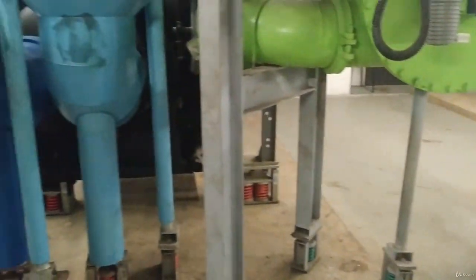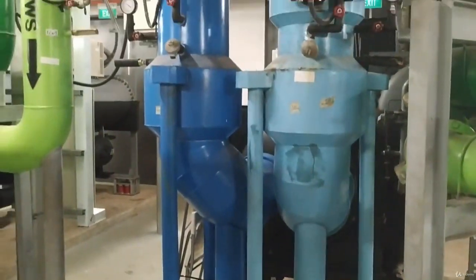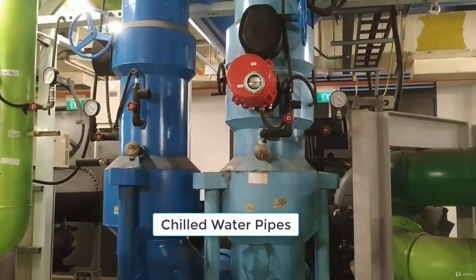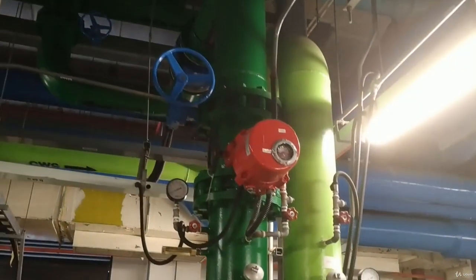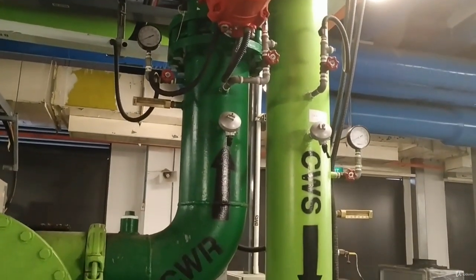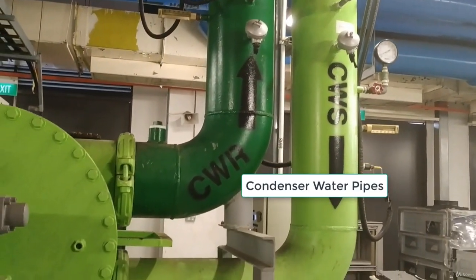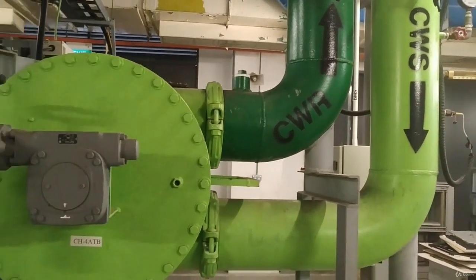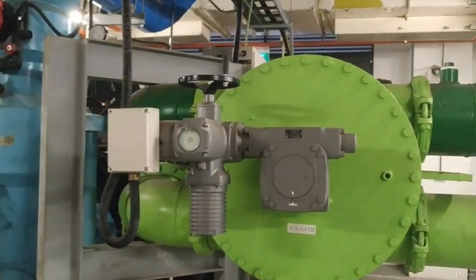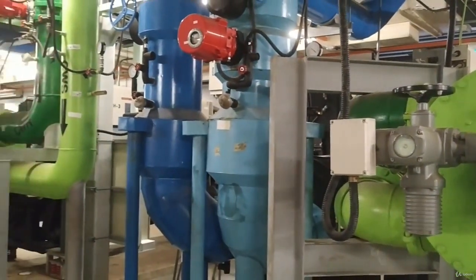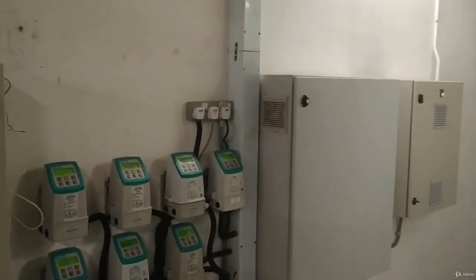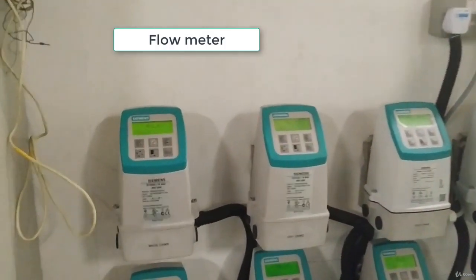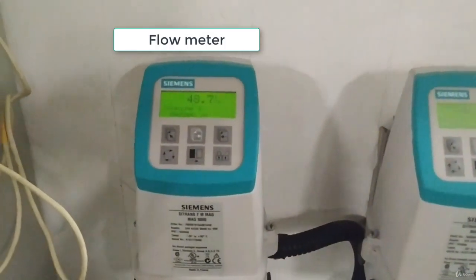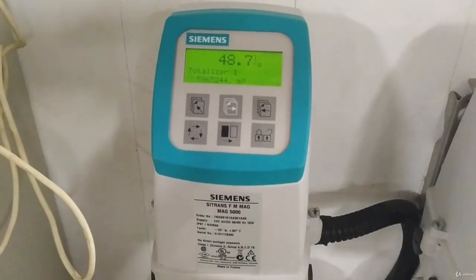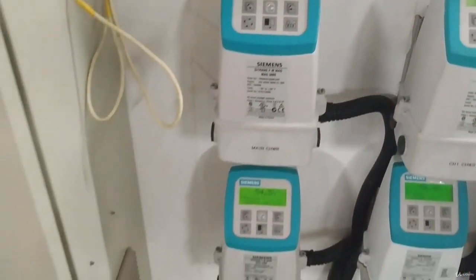At this angle, you can see the chilled water pipes and condenser water pipes connected to the chiller, and connected to the evaporator and condenser shell respectively. The blue pipes are the chilled water pipes and the green pipes are the condenser water pipes. These are the flow meters for the individual chiller, measuring the chilled water flow and condenser water flow.